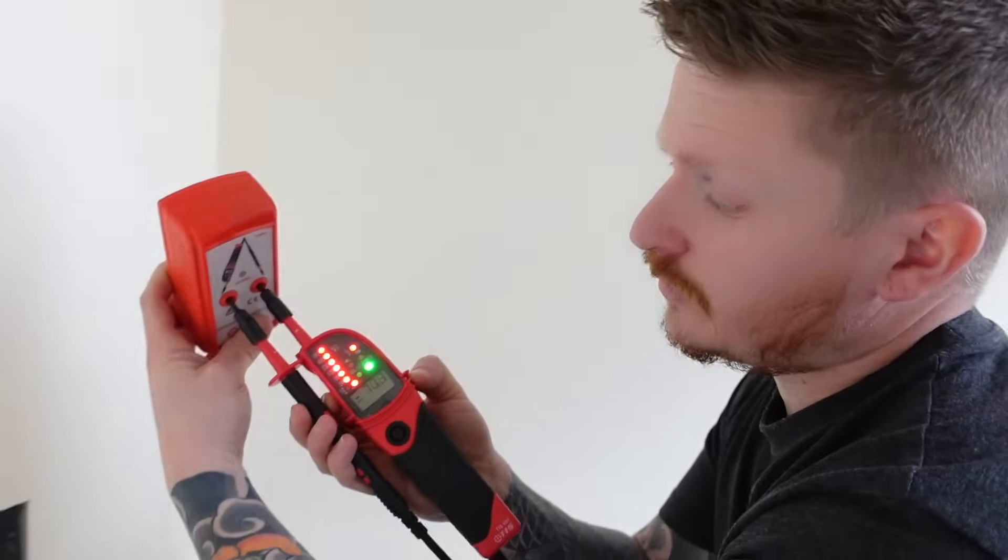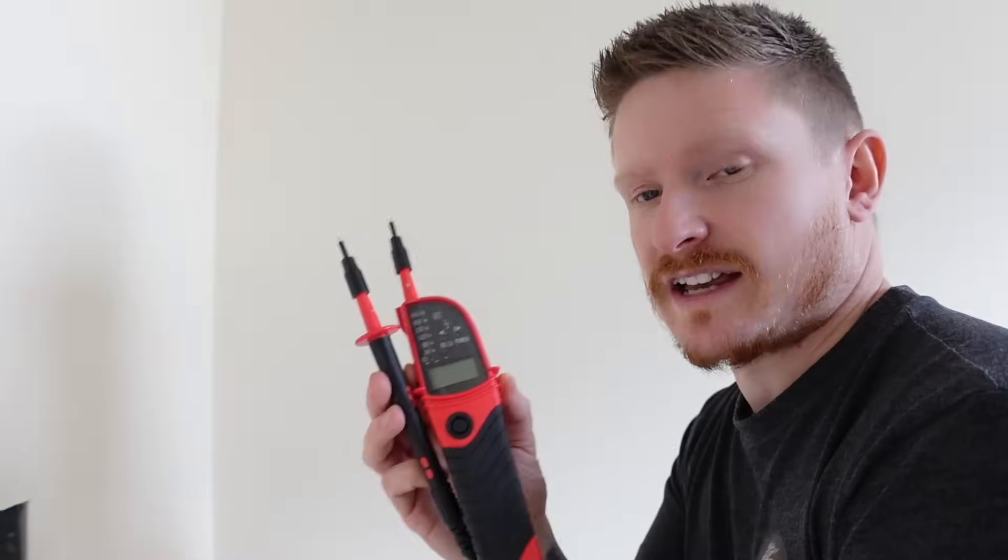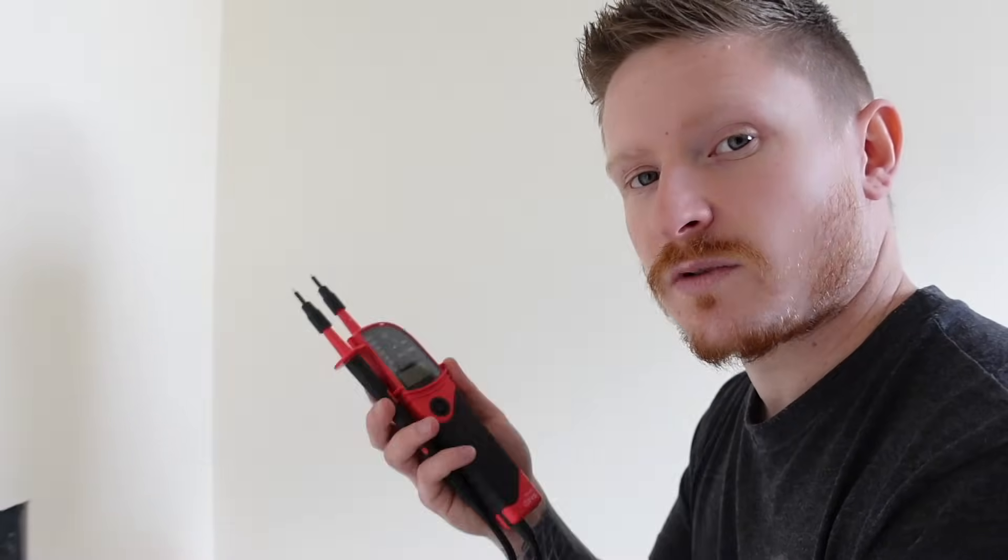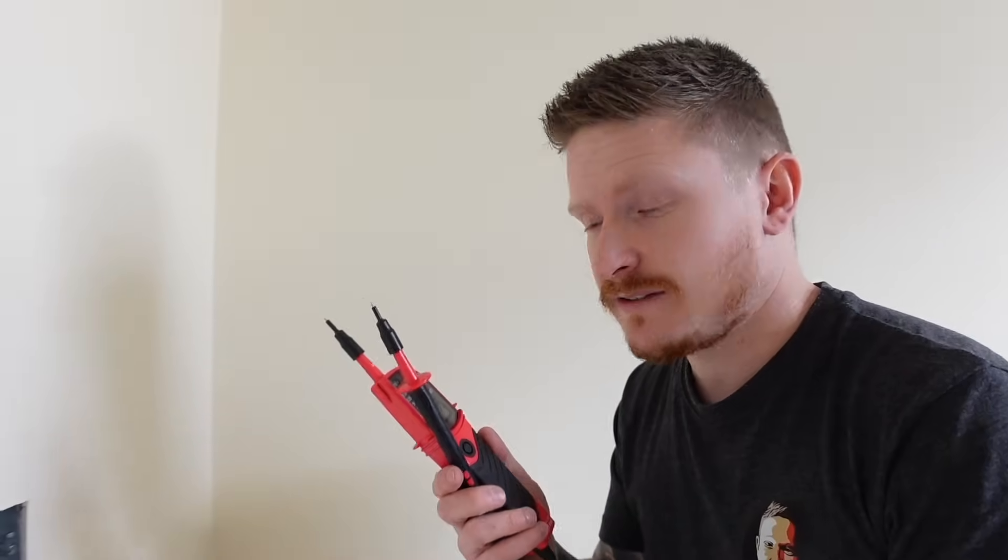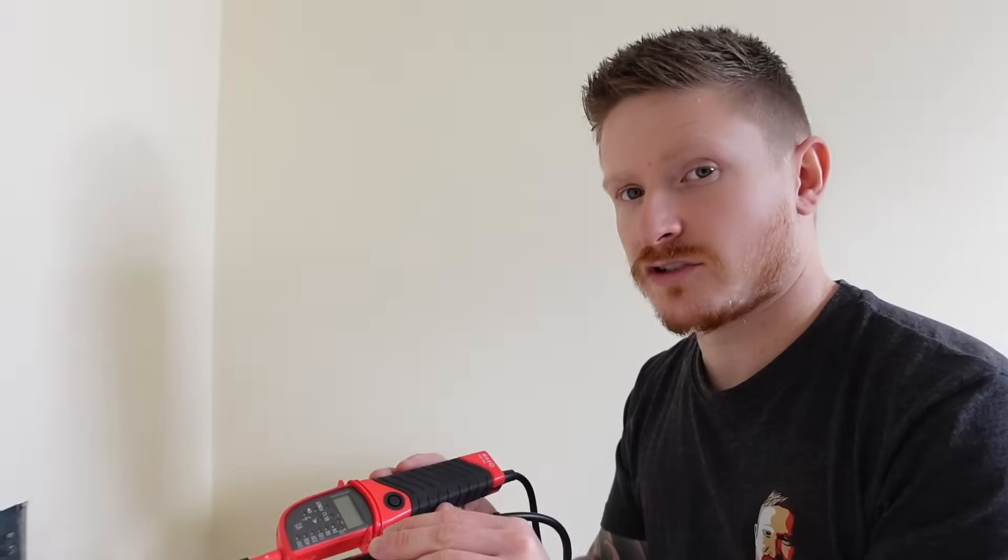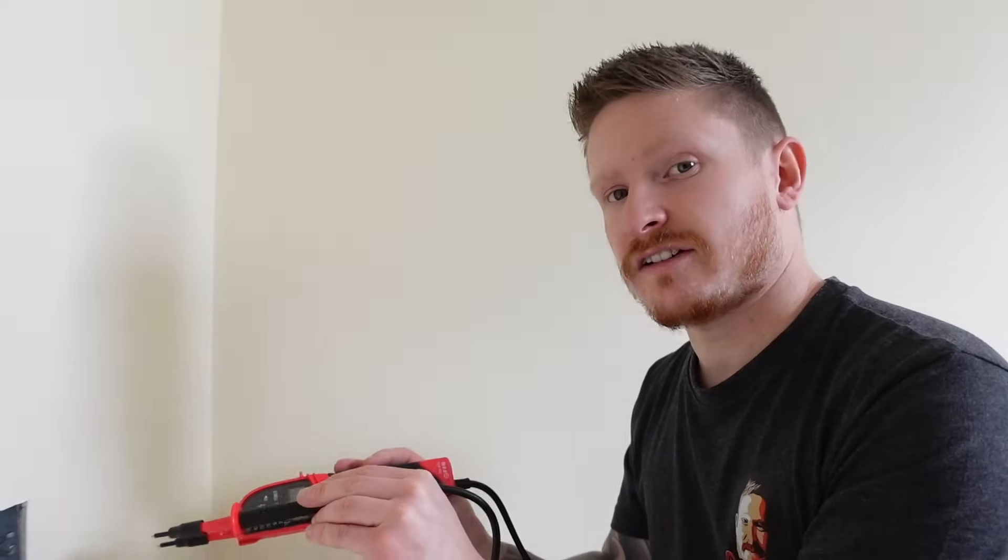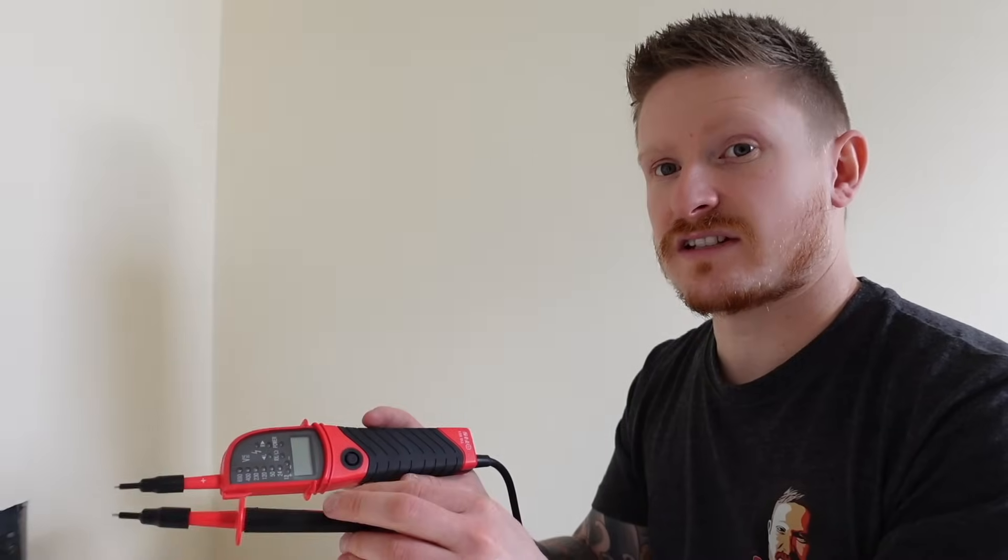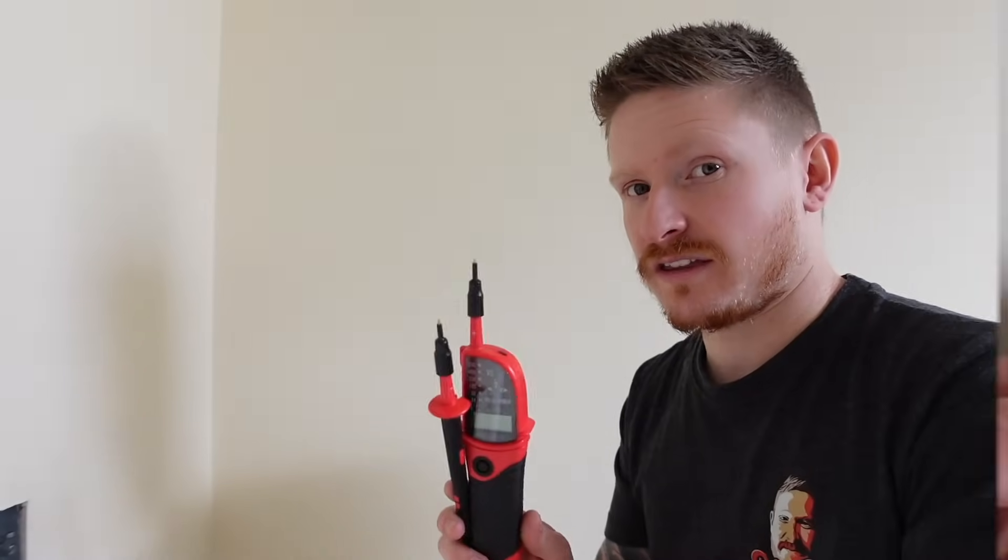We then use the proving unit to test again to check that our voltage tester did not go faulty whilst we were carrying out our test. If you don't have a proving unit you can use a known source of electricity. You would test that on a known source of electricity, you'd then carry out your test and go back to your known source of electricity and that would do the same thing.